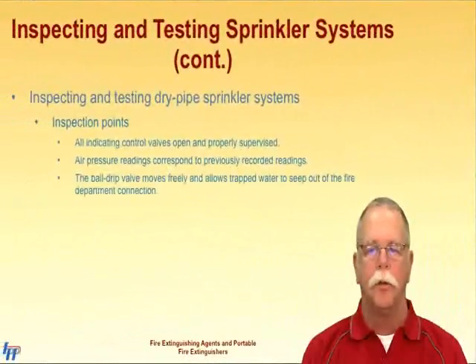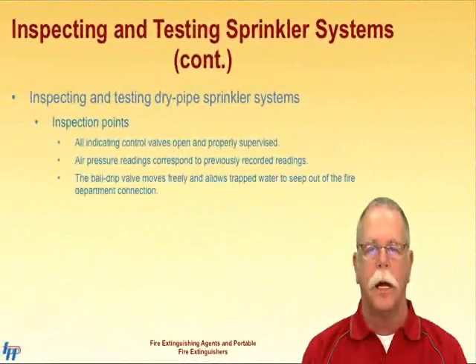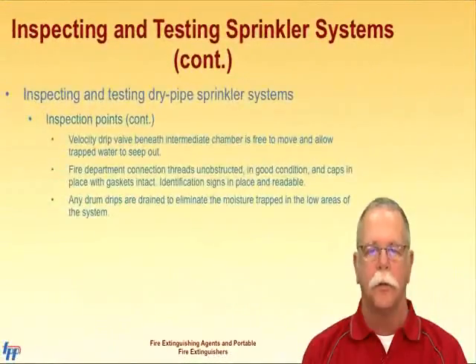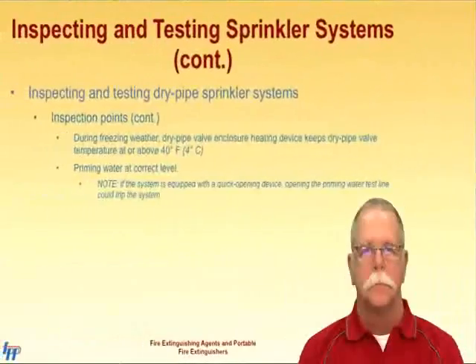Acceptance testing may be witnessed by a representative of the fire department, but a representative from the installation contractor should conduct the test. System tests are conducted by occupancy or contract personnel trained to perform these tests. These tests may also be witnessed by the fire service personnel to verify the records and to make response personnel more familiar with the systems in their area. The test procedures are outlined in NFPA 25, local ordinances, and fire codes.